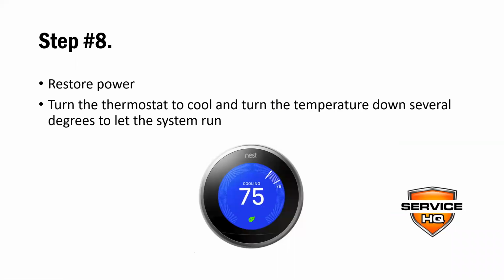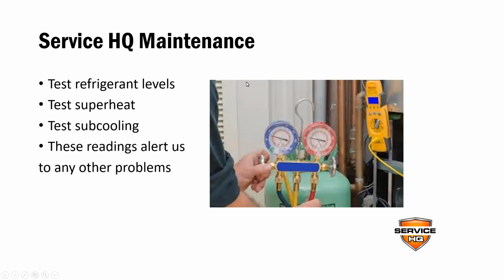So step number 8, we're going to restore power to the system. We'll turn the thermostat to cool and turn the temperature down several degrees to let the system run. Now, for our maintenances, at this point, we're going to test the refrigerant levels. We're going to test the superheat. We're going to test the subcooling. And these readings alert us to any other problems. So once we can look and see what the PSI is on our low side and our high side, or our suction side and liquid side of the system, it paints a picture of what's happening with the system.